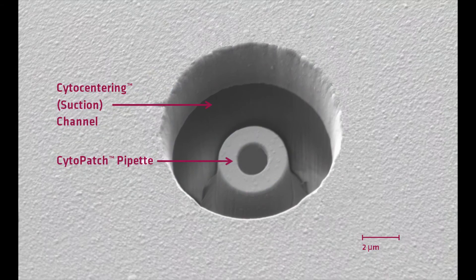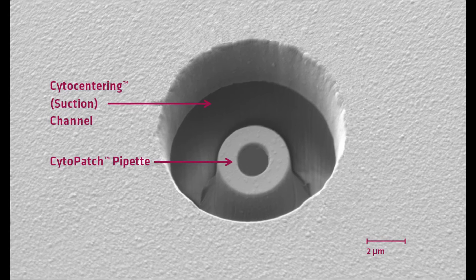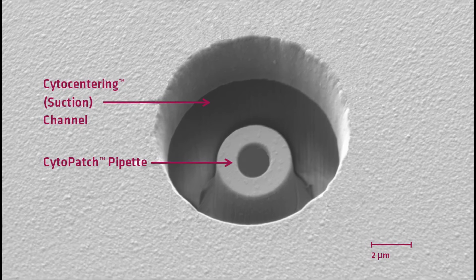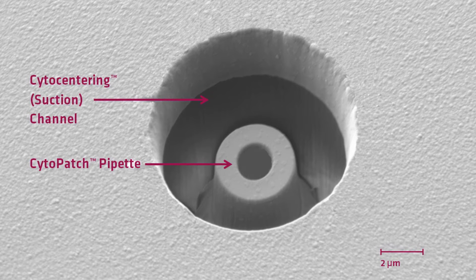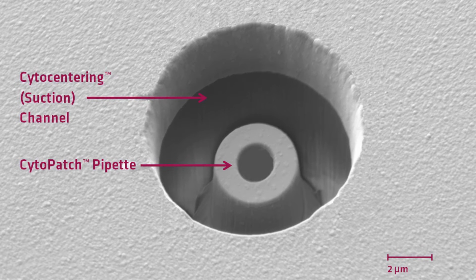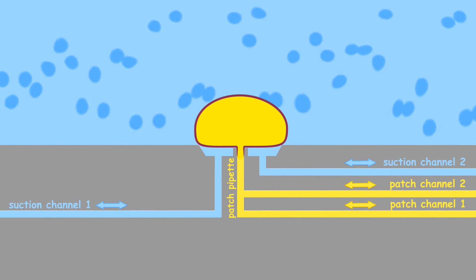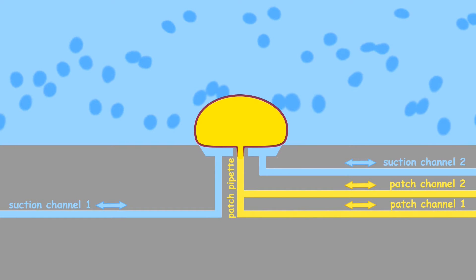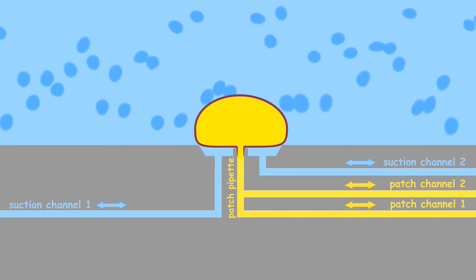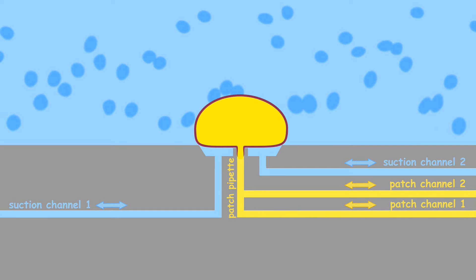At the heart of the instrument lies the Cytopatch chip. The chip contains two independent glass pipettes that are each surrounded by a second channel — the Cytocentering channel. In fact, the Cytopatch provides for having a hole inside of a hole. The outer hole, the Cytocentering channel, is used to position a cell onto the patch pipette, which is the inner hole. Therefore, the pipette stays clean, leading to real giga-ohm seals.